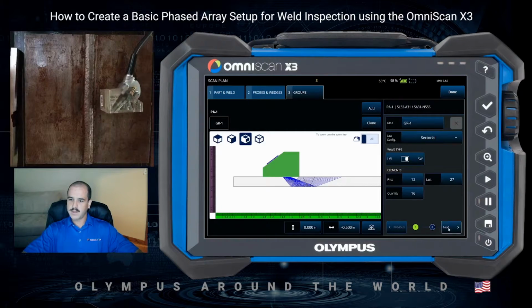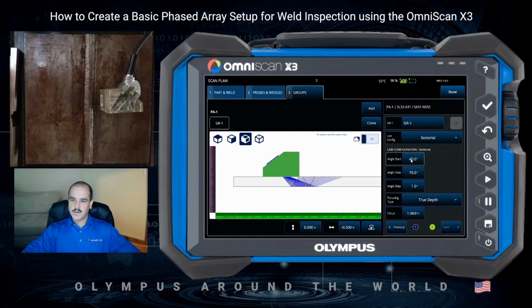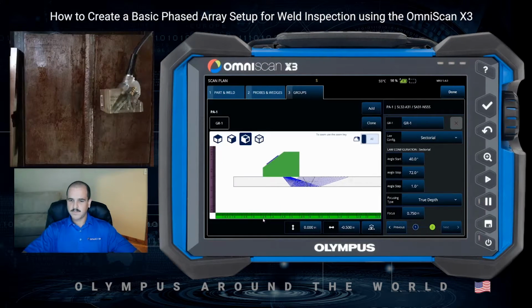So we can go to the next tab here in the bottom right corner. We've got our sectoral starting at 40 degrees, ending at 70 degrees. I'll just bump this up to a 72 to help us in that first leg just a little bit. And we'll use a true depth focus at about 1.5 times the thickness. So we'll do 3/4 of an inch here. And you can see our focal zone pop up in the scan plan. Once that's configured, we can select done.